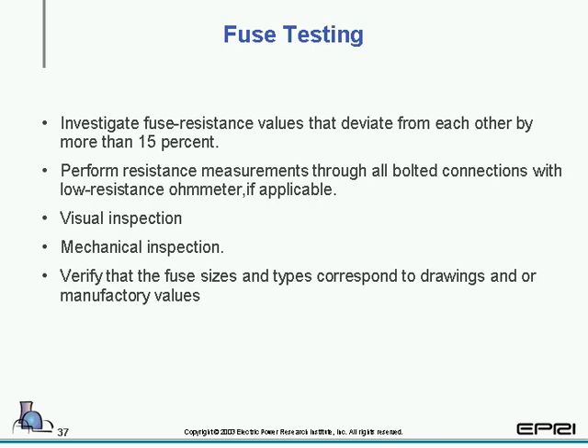Fuse testing. If you have a fuse breaker, you must remove the fuses and shunt them out before you do any high current injection testing. When you're looking at fuses themselves, you want to investigate any fuse whose resistance value measures different from one to the other by 15%.